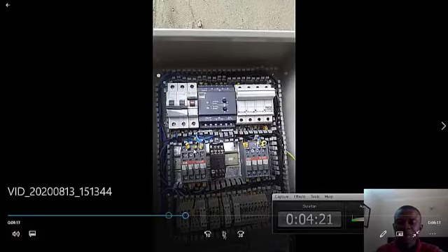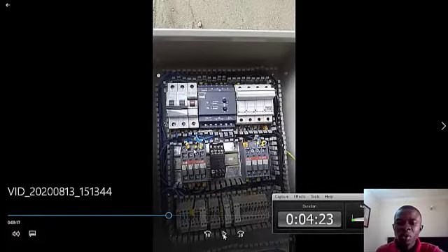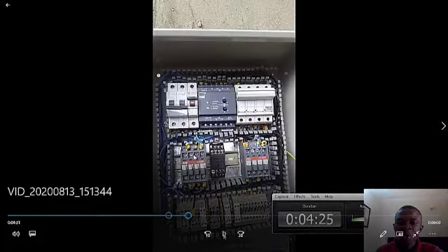As the drawing shows, you run your incomers separately. This one goes on its own from generator com, then this one from NEPA com, and you have your common output. So if any of these closes, your output will go to the building or wherever you assign it to.